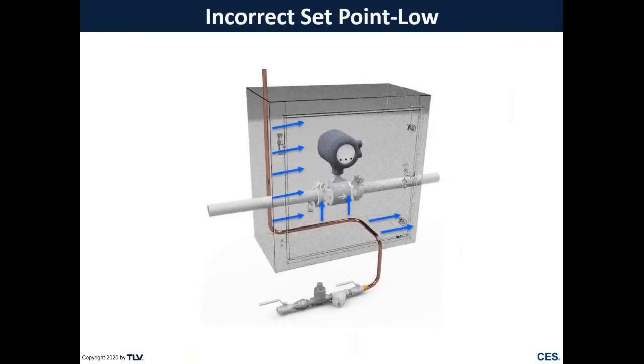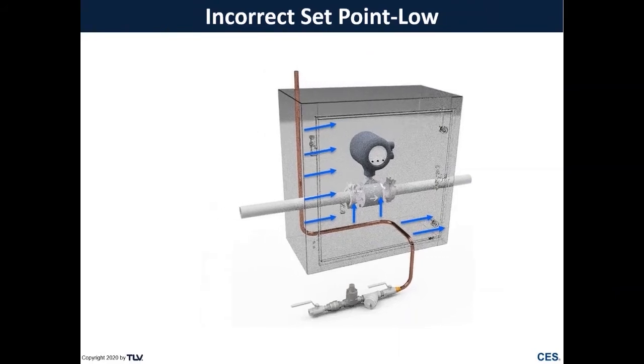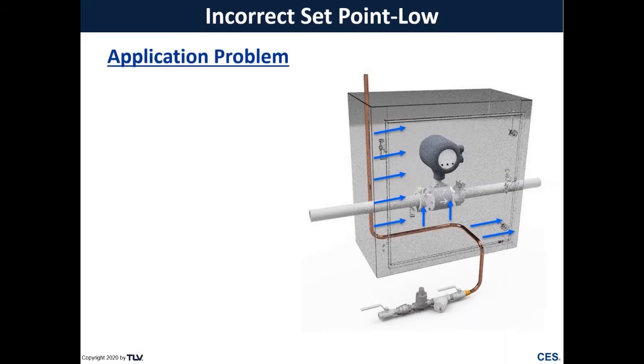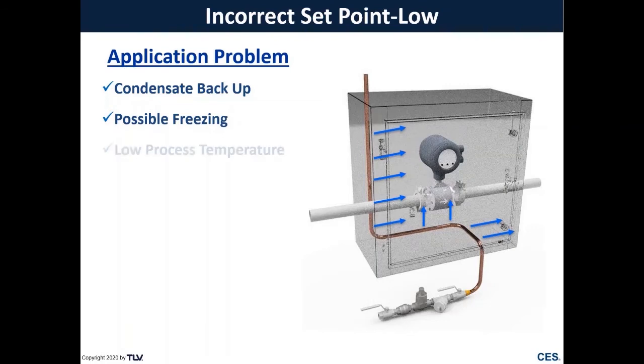Next is an incorrect set point that is too low. Again with an instrument enclosure and a temperature-adjustable steam trap, if it's adjusted too low, it backs up condensate too much and can't provide the heating needed. This can cause condensate to back up, possible freezing in both the tracing line and the instrument enclosure, damaging instruments, and low process temperatures.